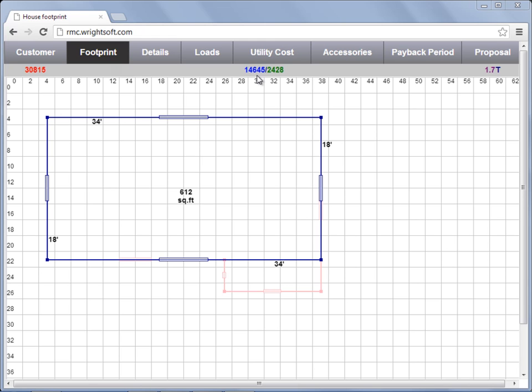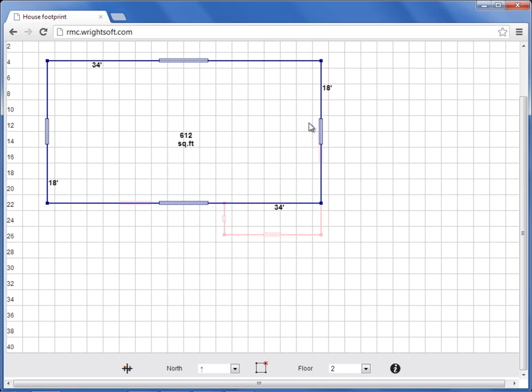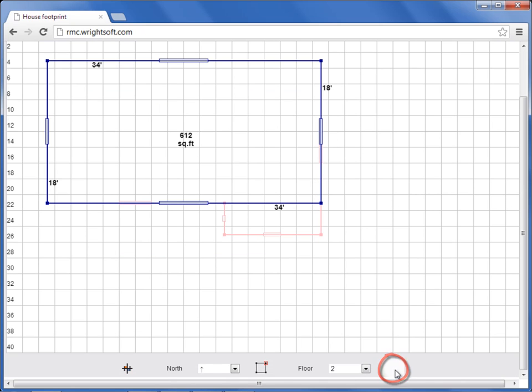Your target tonnage in the upper right hand side is calculated by taking the sensible load in blue and dividing it by the equipment sensible heat ratio. To change your equipment sensible heat ratio, scroll down to the bottom of the footprint and select the I button.